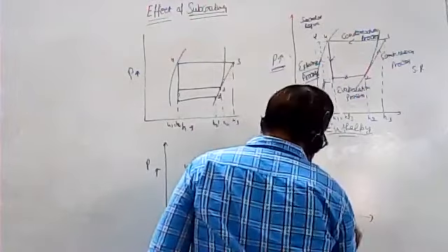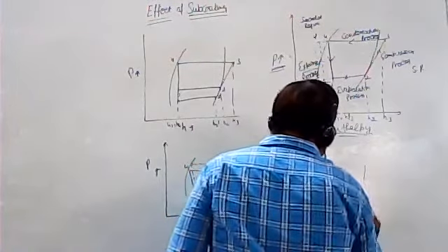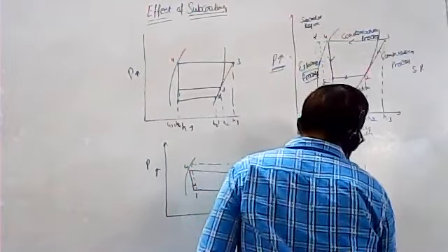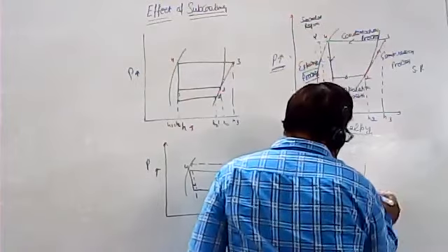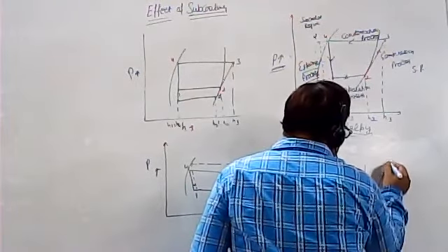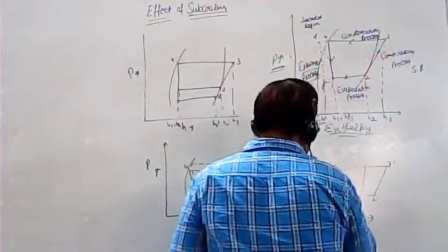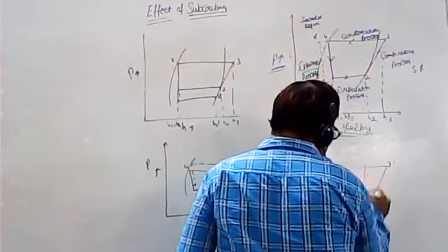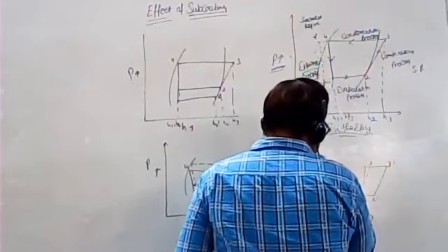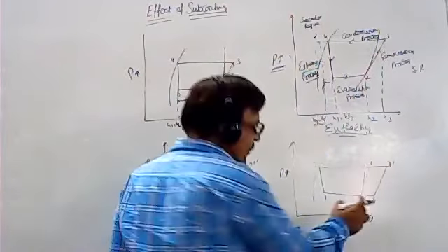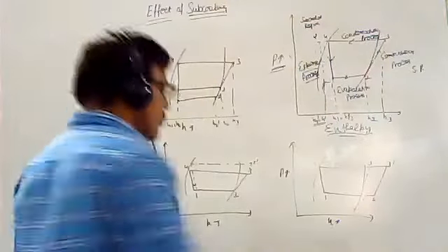Pressure enthalpy diagram, when your vapor after evaporation is in the superheated stage. This much refrigeration effect will get increased, but on account of the increase in the work done by your compressor, overall your COP will get reduced in this case.